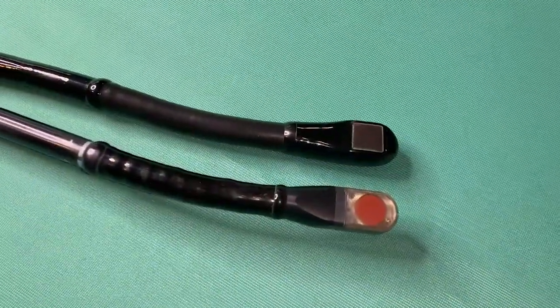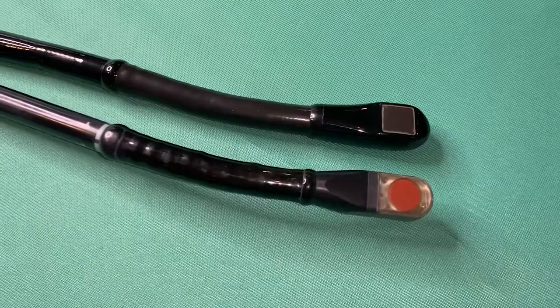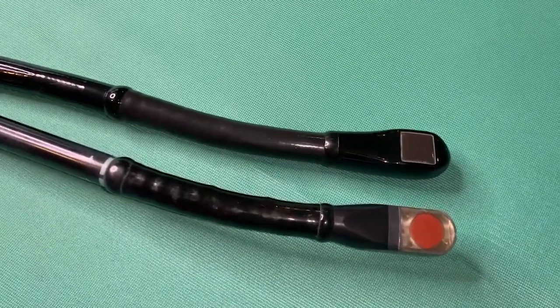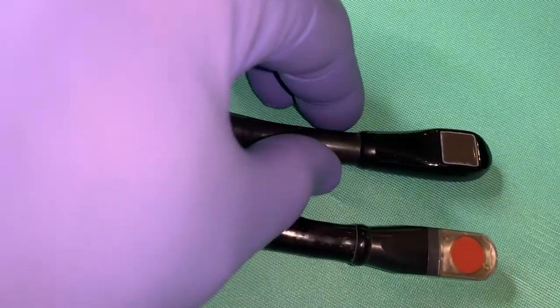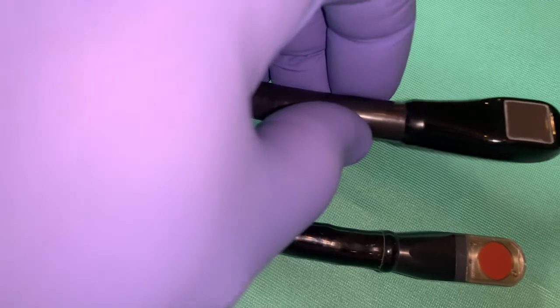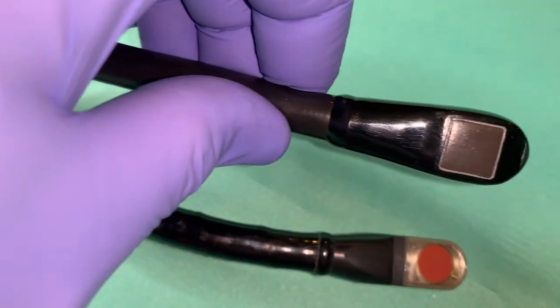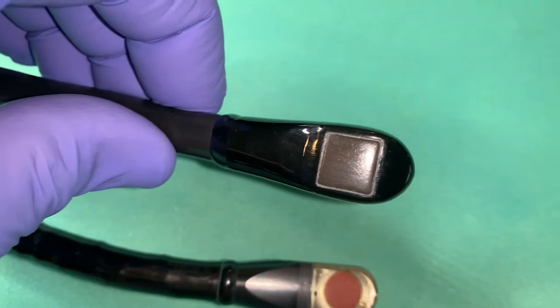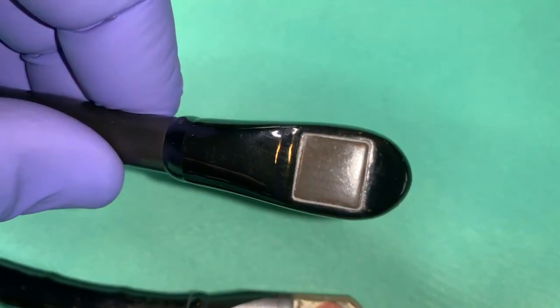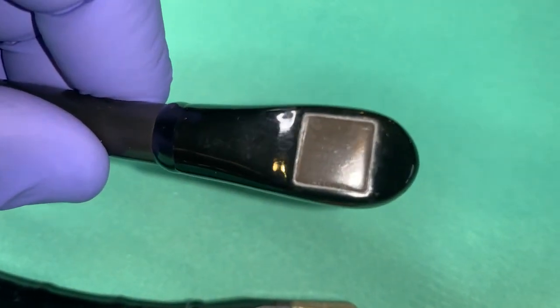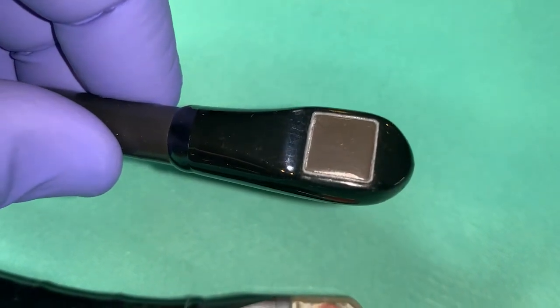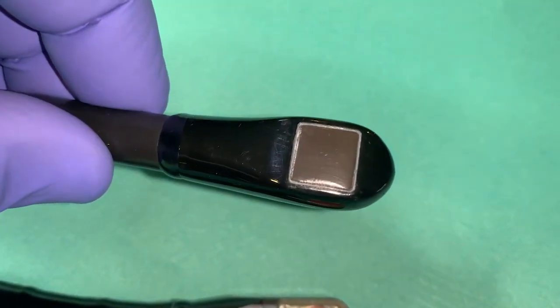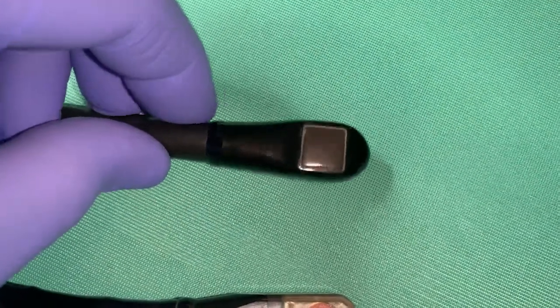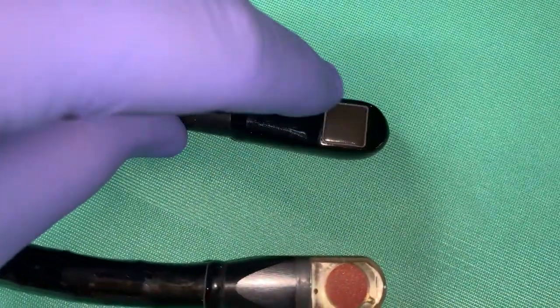The acoustic lens covers the acoustic array, which is a highly sensitive component similar to the camera in a flexible endoscope. There are 2 styles of lenses on TEE probes which are descriptive of the probe's level of technology. 3D probes, such as the Philips X72T and X82T and the GE6VTD and Siemens Z6M, will have a square or rectangular shaped lens. The lens will have a rubber-like appearance and may be surrounded by a gray or white sealant.